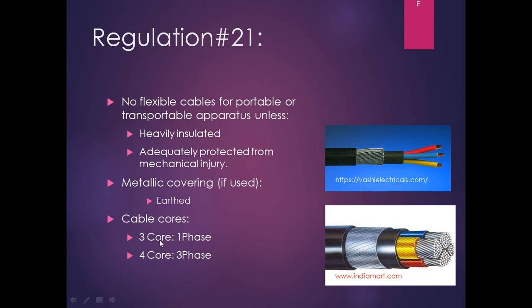For single phase we should use 3-core cable, and for 3 phase we should use 4-core cable. The idea behind this is that for movable and transportable apparatus, the neutral cable and phase cable should go through the same outer sheath, or they should be concentric. The reason is that if some electrical fault develops between the two cores or at the internal insulation, they should short each other. That means neutral should short with the phase or phase should short with the phase inside the cable only.